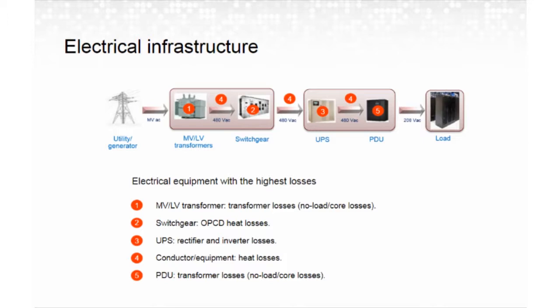The next thing is the conductor. There are heat losses involved with the conductor. And then the fifth part is a PDU, or basically a transformer, again, that steps it down to the 208 volts. Again, no load or core losses.